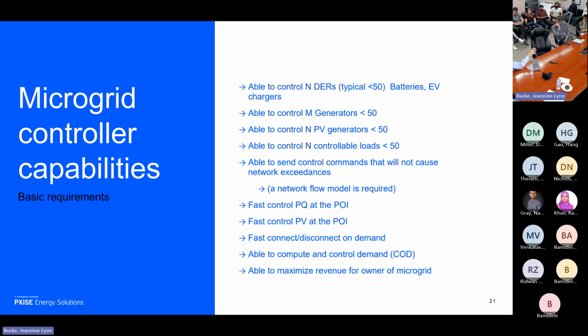How do we control? By the way, when you're in microgrid mode, your inverter is in voltage source mode. That means I can send frequency signals and voltage signals to the inverter. Now, I'm not going to send it a voltage signal because the voltage is where I want it to be. But I'm going to give it a little bump in frequency from 60.000 to 60.050. What's that going to do? The angle is going to change at 18 degrees per second until I get to the real power that I'm asking for. Also, that angle is going to change to the angle of the main grid.